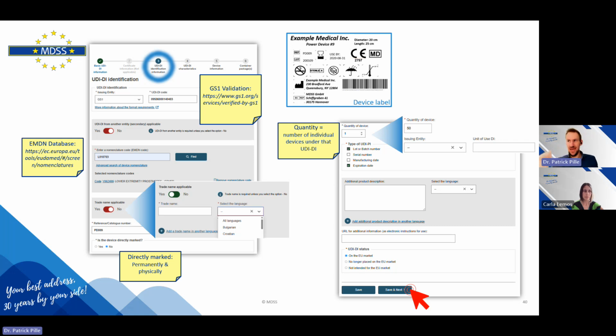One aspect to that: if you have the IVDR or MDR certificate already, or expect it very soon, and if the legacy and regulation devices have the same device identification—meaning the UDI-DI, the same catalog number, or the same trade name—the regulation is quite nice in this regard. They have a wide definition of what counts as the same identification. In that case, it is sufficient to register only the regulation device, even though both legacy and regulation versions are placed on the market.